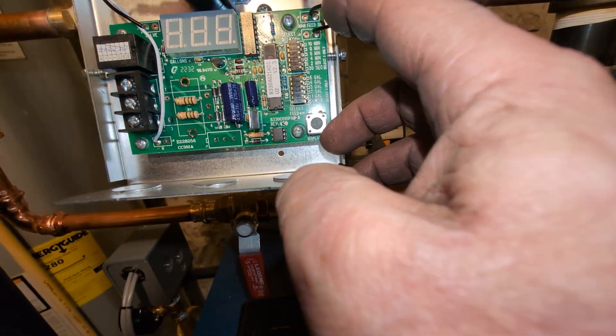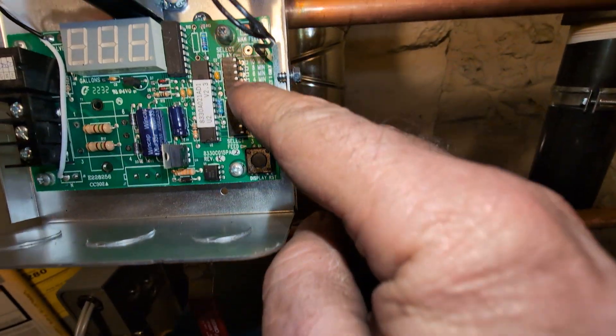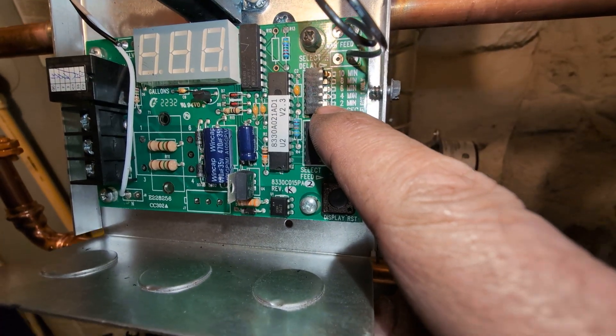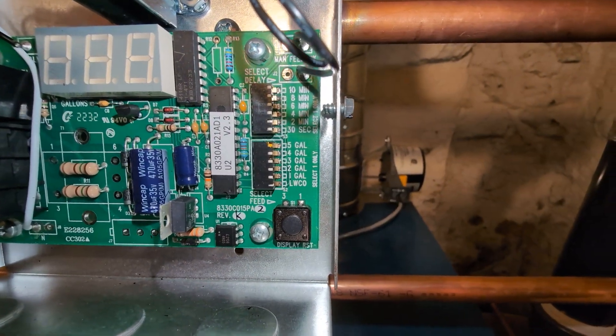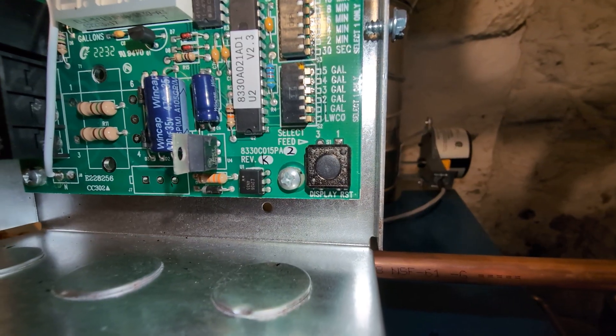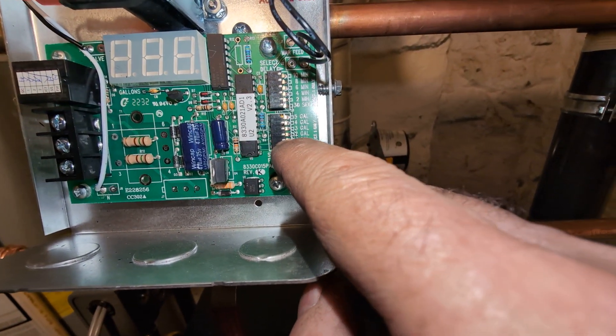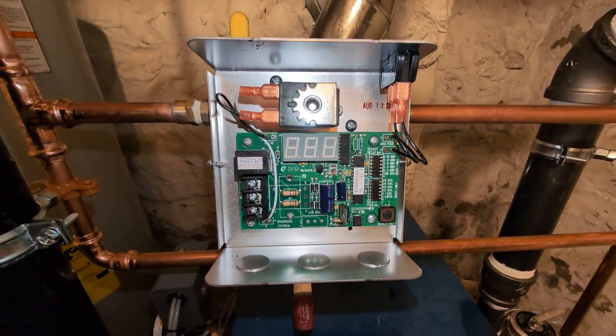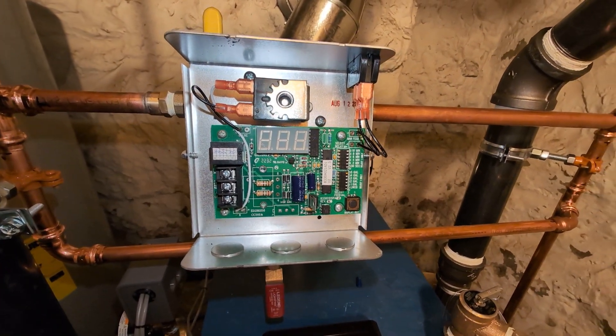Right now it comes set from the factory at a two-minute delay — that dip switch there is depressed and it's set for low water cutoff. We're going to probably change that to a one-gallon, two-minute delay and see how that works out.